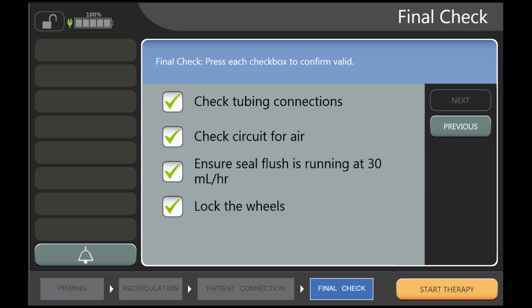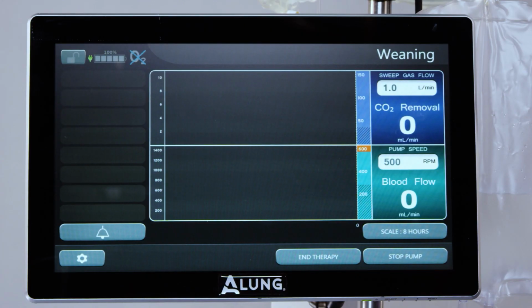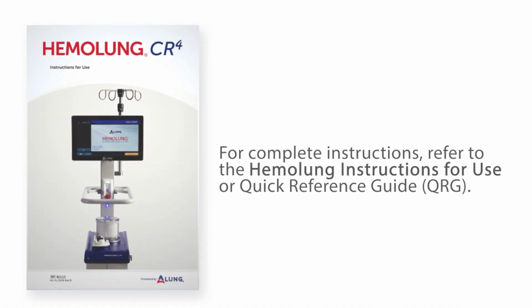Before starting therapy, check tubing connections. Check circuit for air. Ensure seal flush is running at 30 milliliters per hour. Lock the casters. Press Start Therapy. The pump will start automatically at a speed of 500 revolutions per minute. For complete instructions, refer to the HEMOLUNG RAS instructions for use.